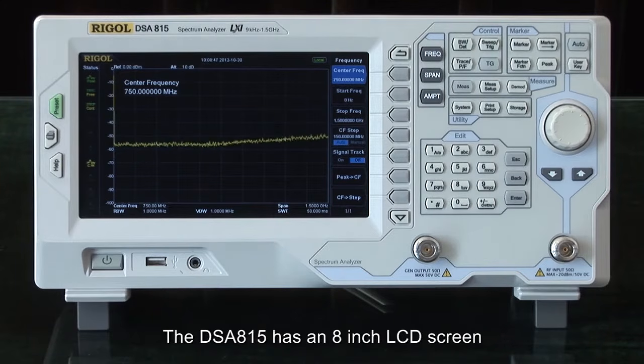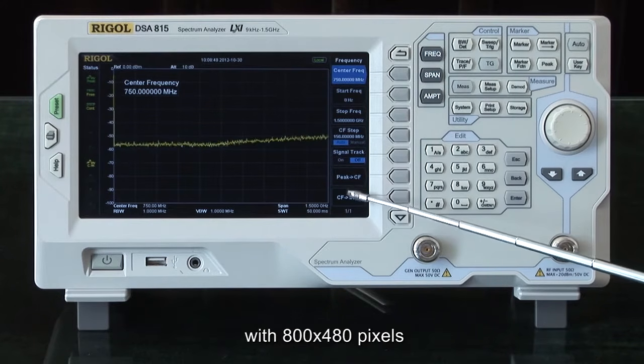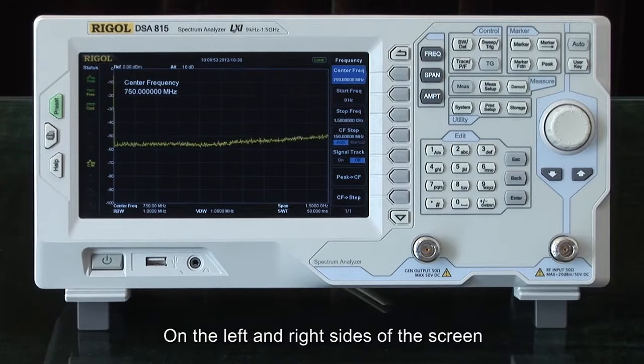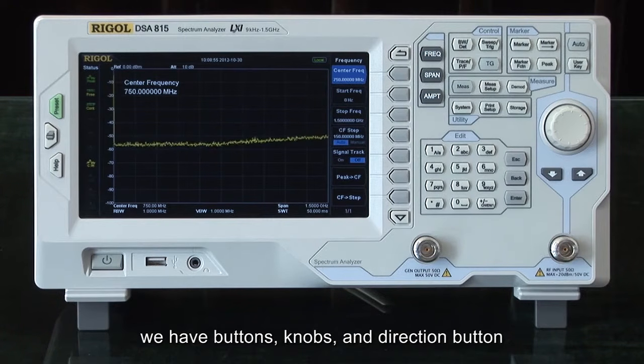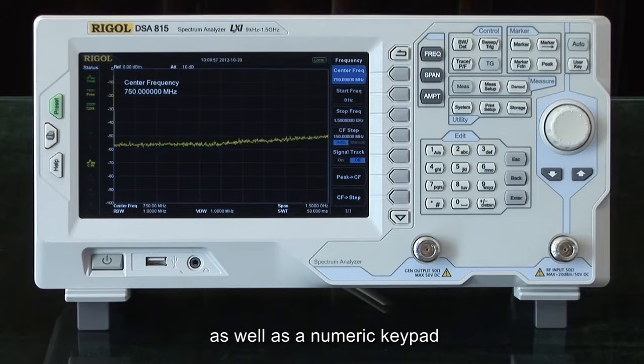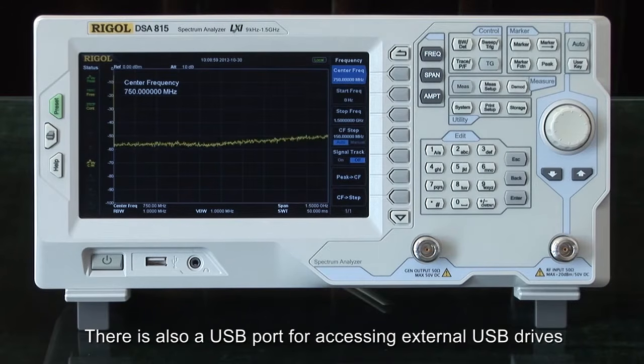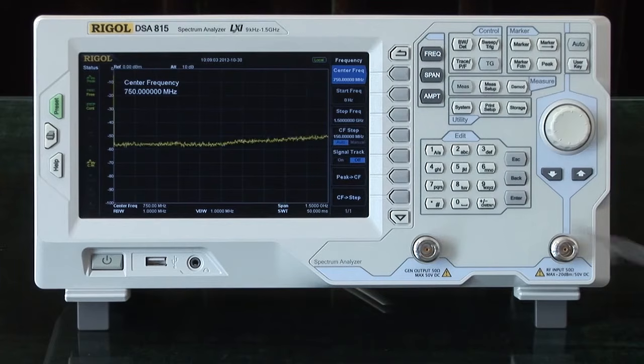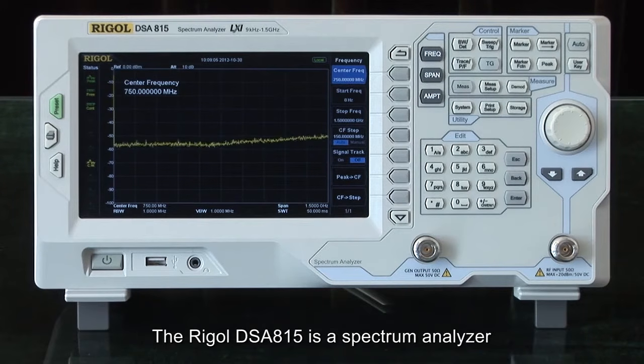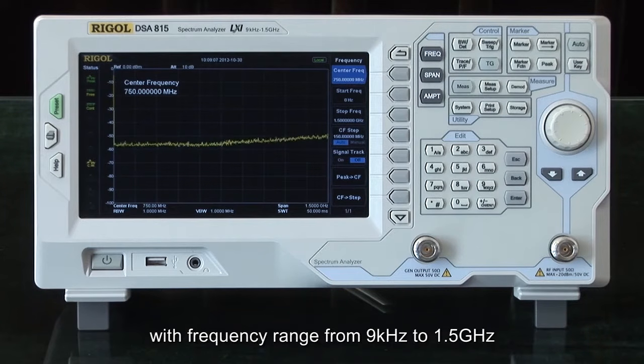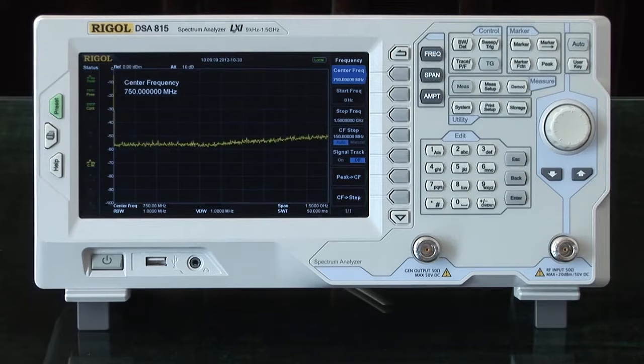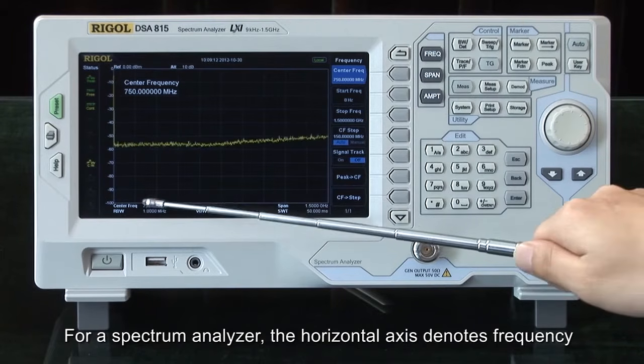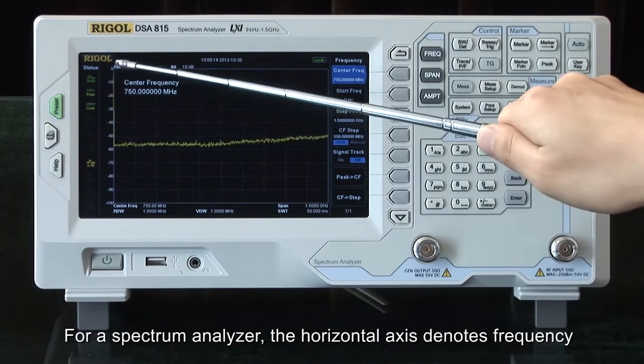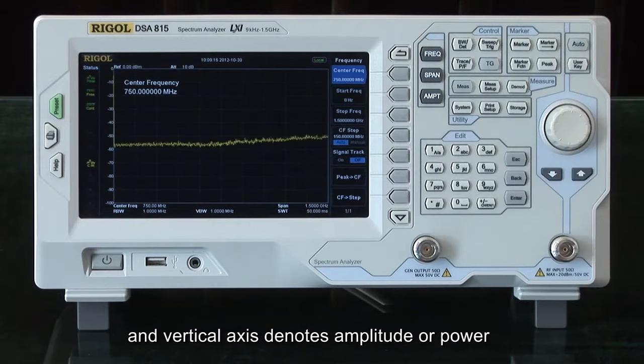The DSA815 has an 8-inch LCD screen with 800 by 480 pixels. On the left and right sides of the screen, we have various buttons, knobs, and a direction button, as well as a numeric keypad. There's also a USB port for accessing external USB drives. The Rigol DSA815 is a spectrum analyzer with frequency range from 9 kHz to 1.5 GHz. For a spectrum analyzer, the horizontal axis denotes frequency and vertical axis denotes amplitude or power.